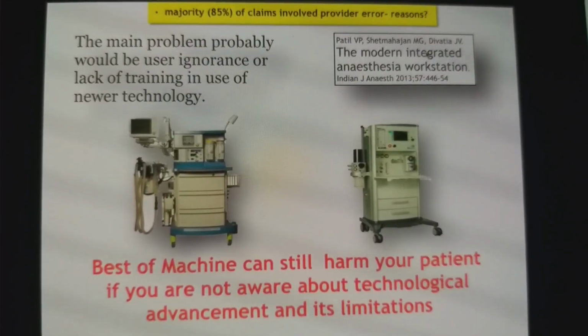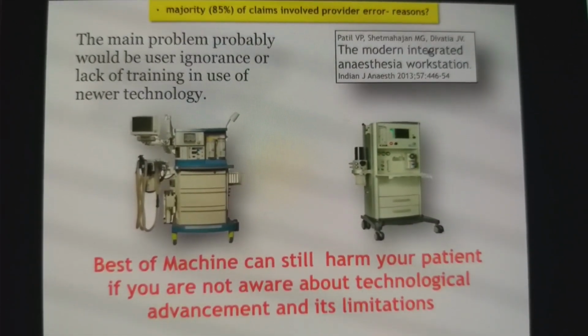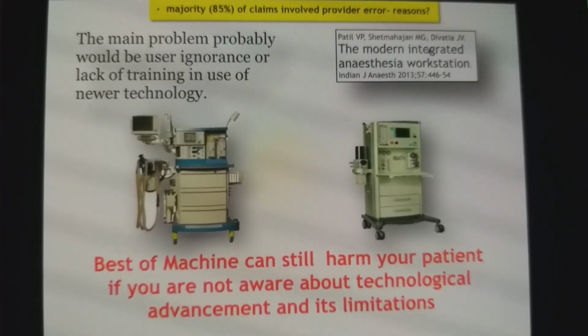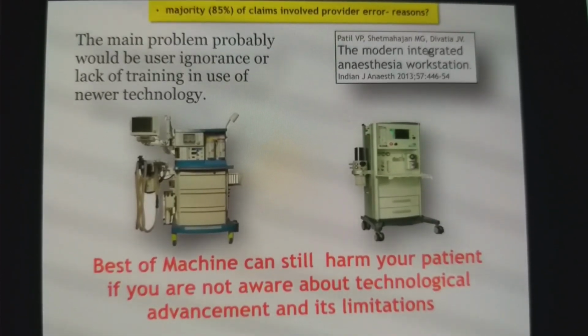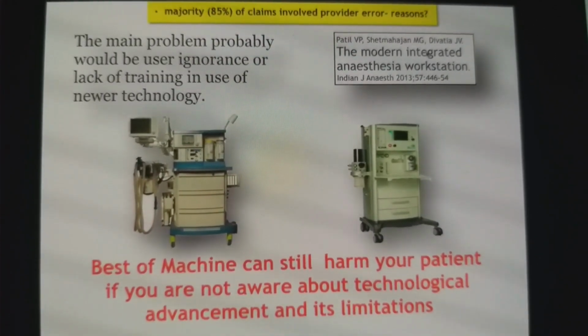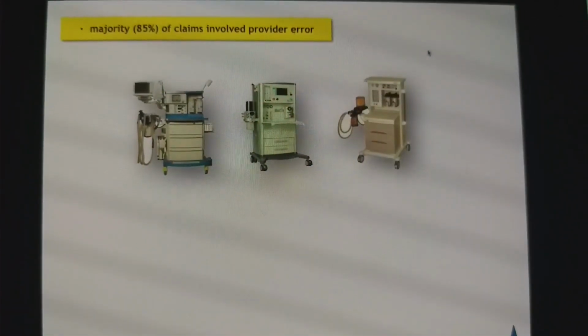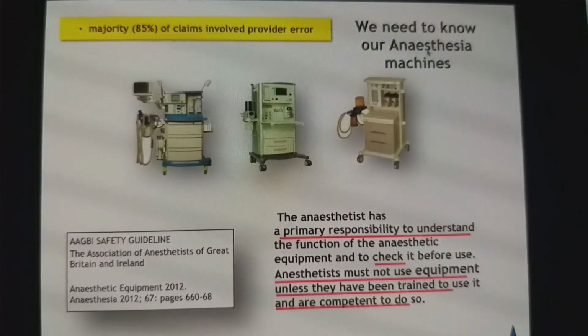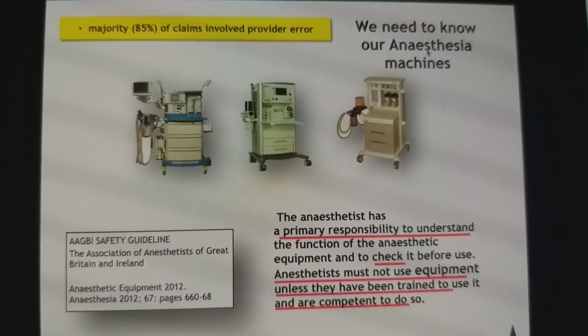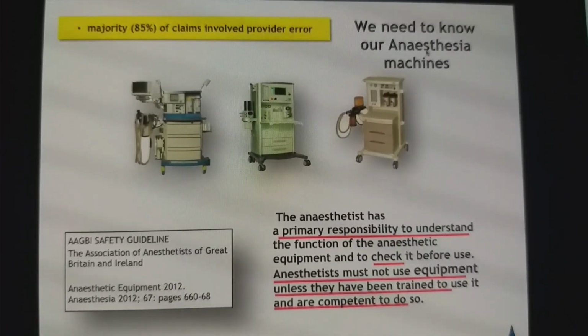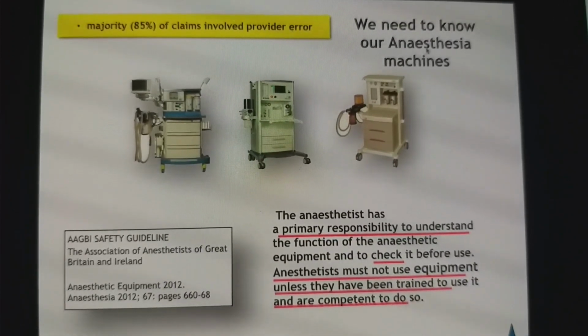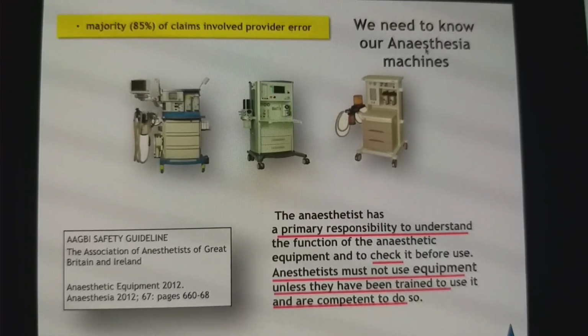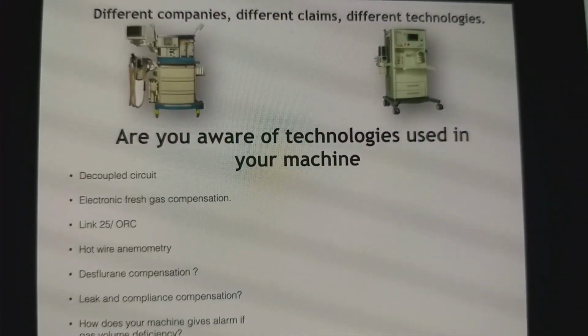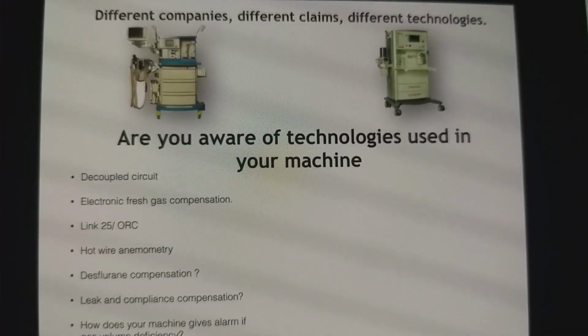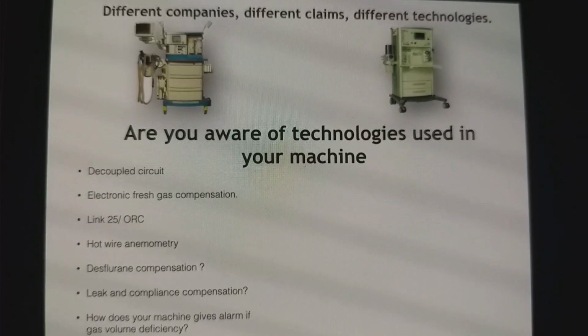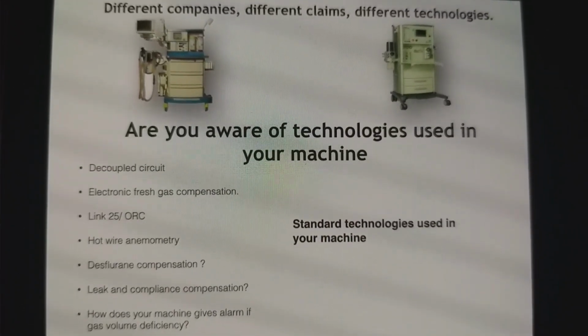So the main problem is probably users' ignorance or lack of training in the use of newer technology. Even the best anesthesia machine can still harm your patient if you are not aware of technological advancement and its limitations. So the prime responsibility is to understand the function of anesthetic equipment and to check it before it's used, and you must not use equipment unless you have been trained to use it and are competent to do so. Looking at the questions which I asked you, the majority of you are not aware of this technical part of your anesthesia machine. These are the standard technologies which are used in your machine.